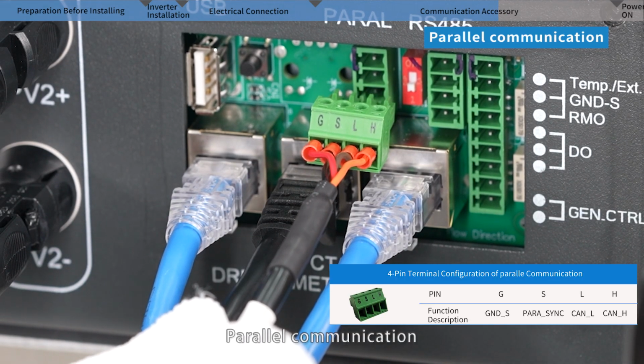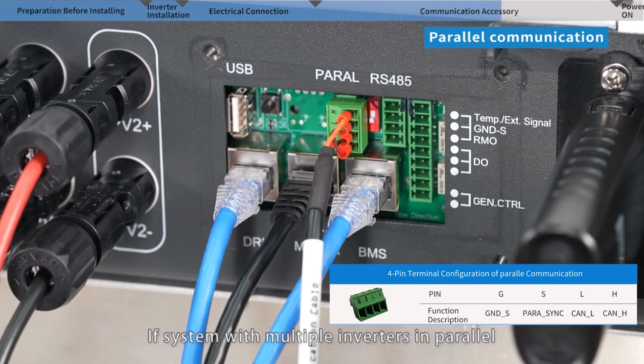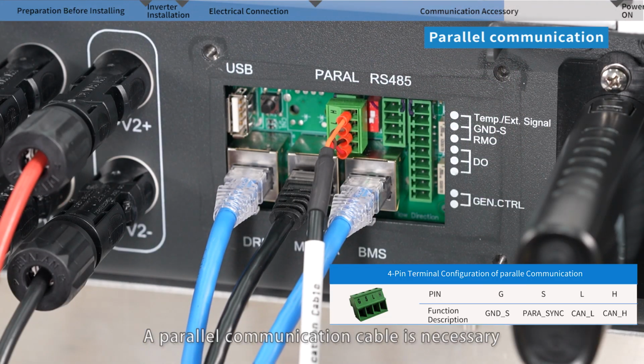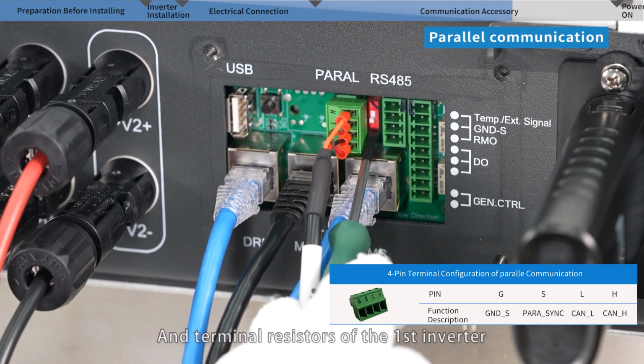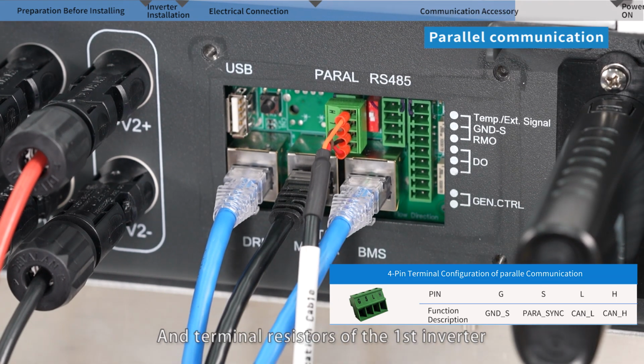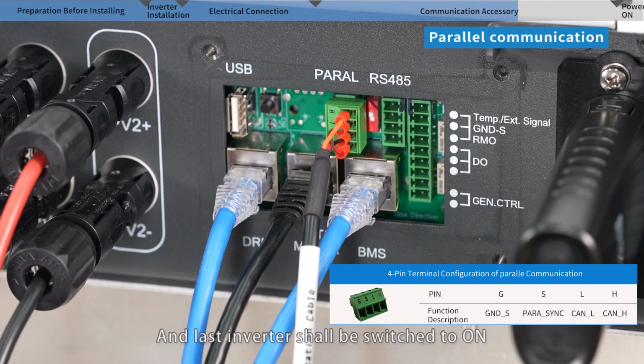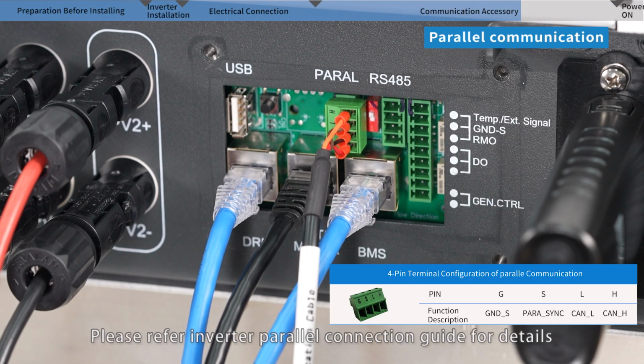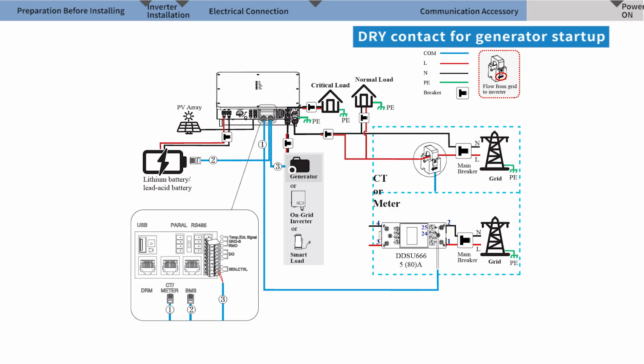Parallel communication. If the system has multiple inverters in parallel, a parallel communication cable is necessary. All 4 pins of the parallel connector are needed, and the terminal resistors of the first inverter and last inverter shall be switched to on. Please refer to the Inverter Parallel Connection Guide for details.